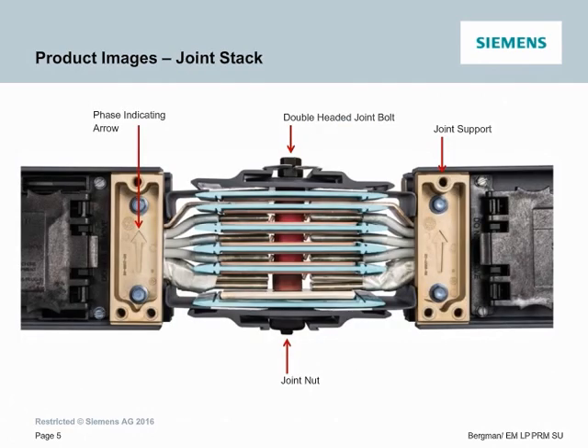Here we have an image of the joint stack. The phase indicating arrows are an important user feature and indicate the phasing of the busway. The joint covers have these same arrows, which must point in the same direction, thus ensuring correct installation. The second head of the double-headed joint bolt shears off during installation when proper joint torque is reached.